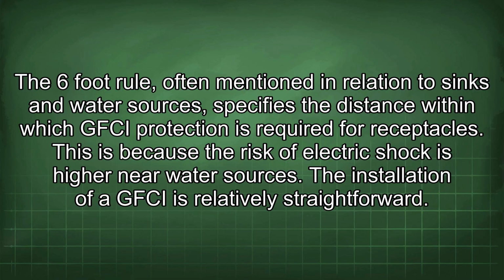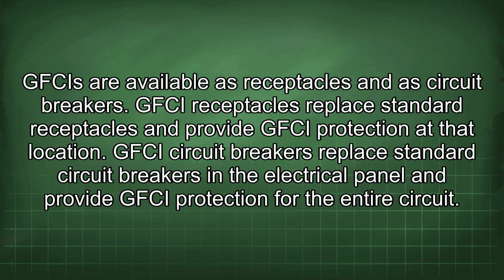The installation of a GFCI is relatively straightforward. GFCIs are available as receptacles and as circuit breakers. GFCI receptacles replace standard receptacles and provide GFCI protection at that location. GFCI circuit breakers replace standard circuit breakers in the electrical panel and provide GFCI protection for the entire circuit.